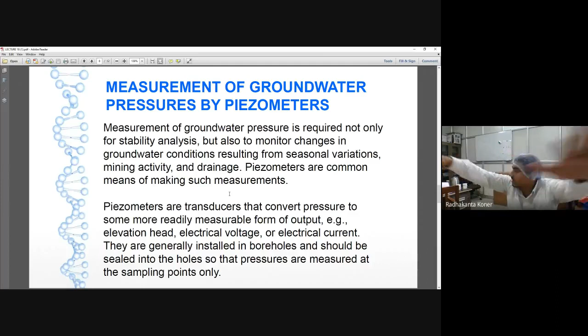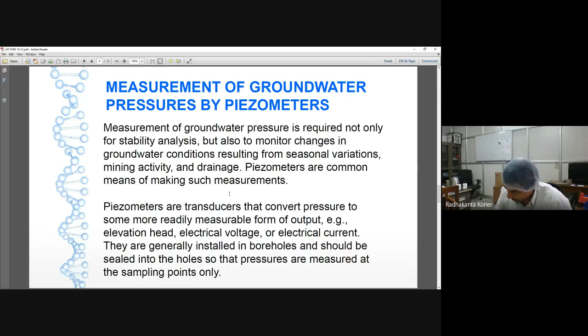Yes, this is the amount of net groundwater flow, and if this groundwater flow is coming into the mine open pit, we estimate how much water will come, and based on that we can design the pump capacity to evacuate that amount of water. So this piezometer converts the pressure to a more readable output, in the form of elevation head, electrical voltage, or electrical current, based on the different systems we follow.